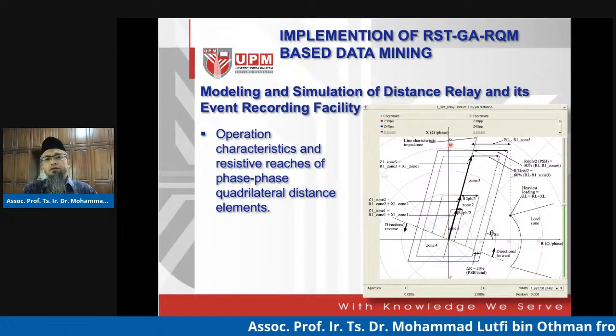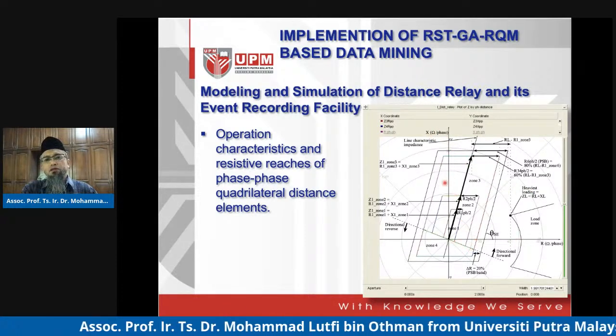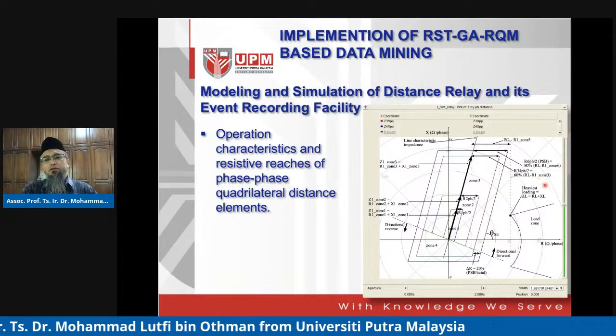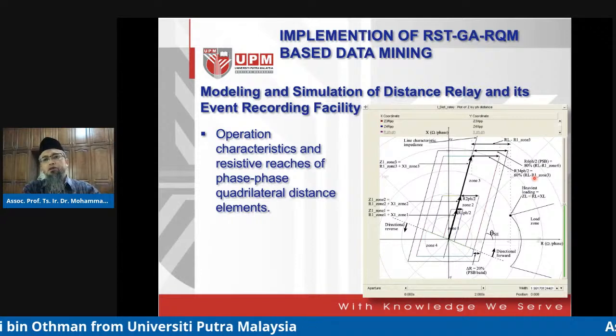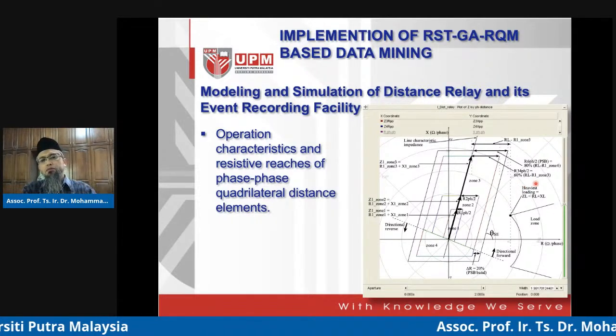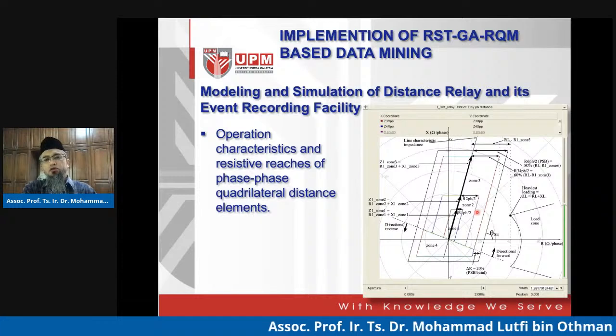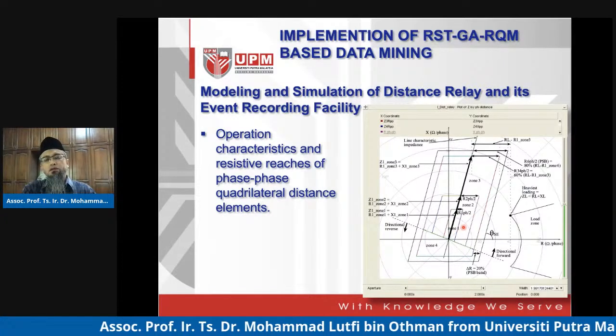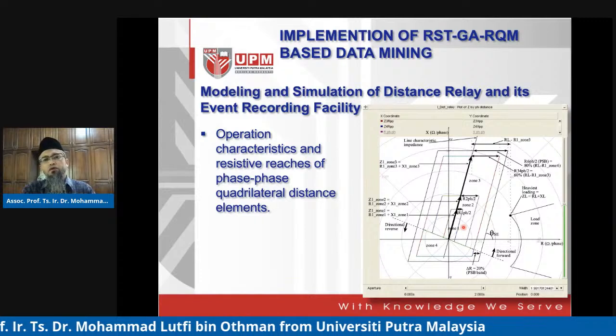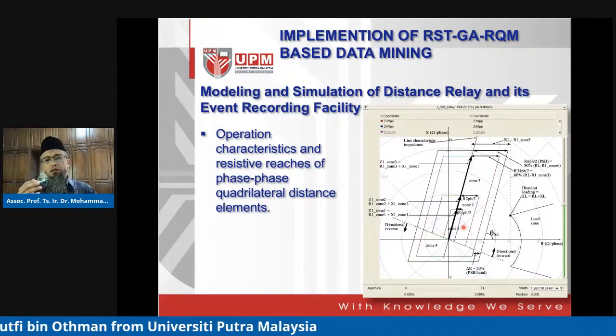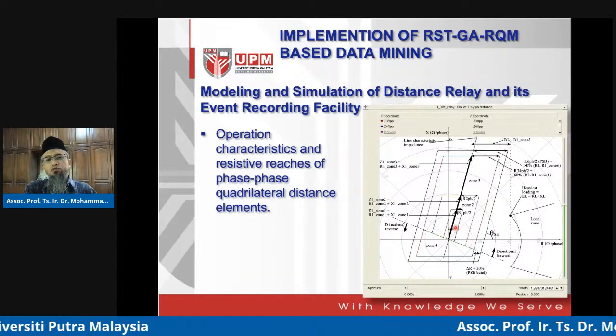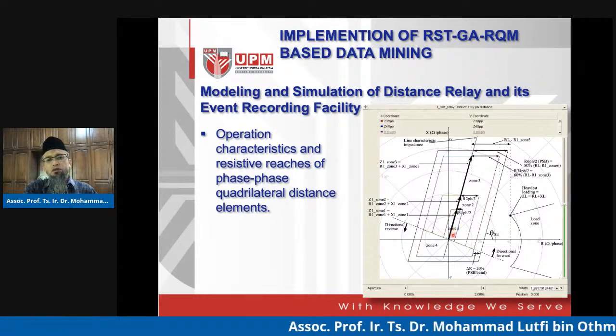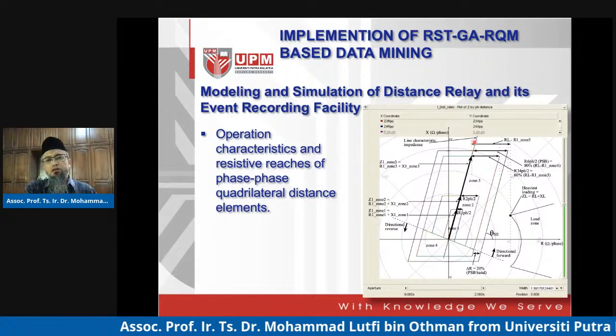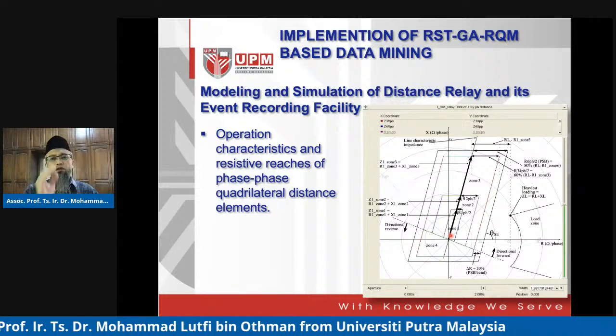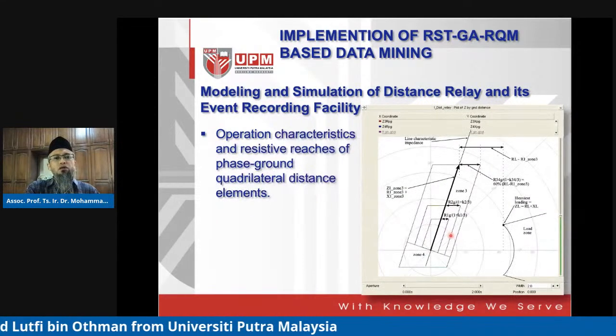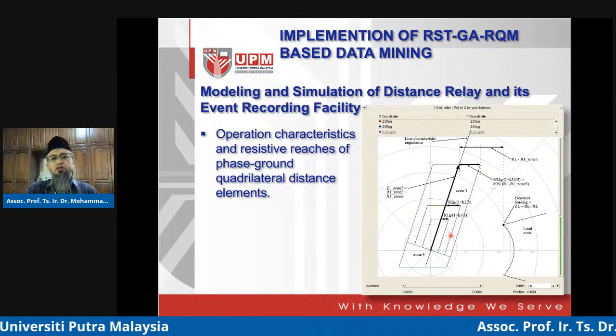So what we want to see here is the trajectory. This is an impedance plot, so you are talking about the impedance trajectory of the transmission line. The impedance is measured, and when there is a fault, the impedance would immediately go into the zone that is of importance. For example, if the fault is located very close to the distance relay, then it would immediately go into zone 1 because it is very close. This is the position of the distance relay. This line shows the direction of the fault along the transmission system. That is phase-to-phase. This is a ground-to-phase operation characteristic.